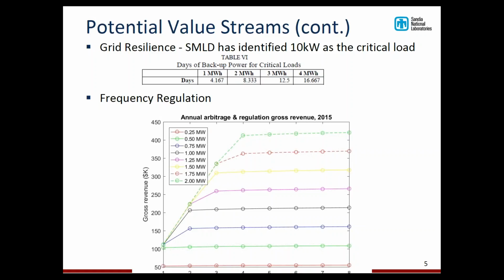And then we looked at frequency regulation as the last potential value stream. For this, we did some optimizations with market data from several years. This plot shows just 2015 data. The bottom of the chart, which is a little cut off, it looks like, in the slide presentation, the x-axis is the capacity in megawatt hours, and the y-axis is the gross revenue in hundreds of thousands of dollars. So one thing you'll notice is that there's a knee in the curve for all the plots, and we go from a 0.25 megawatt system all the way to a 2 megawatt system.